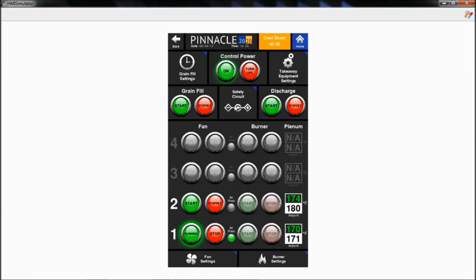In this specific scenario, where we had a takeaway overflow, the discharge would stop immediately. The grain fill would continue to follow any timers. So we try to shut it down in the softest way we can, and then once the timer finishes, we would shut everything else off. Now, if you're on site when you have a shutdown like this, if you come up to the screen and you see that you're in the middle of a cool down and your fan's still running, you may know what the problem was and be able to address it and try to get the dryer running prior to the dryer shutting down.